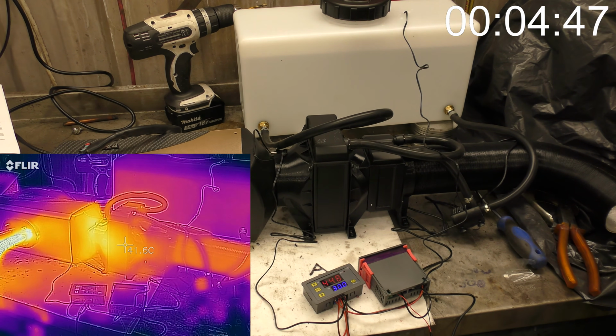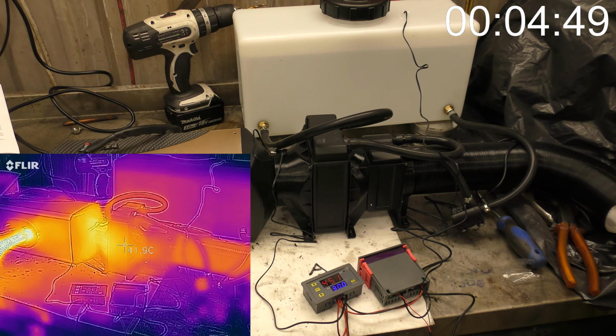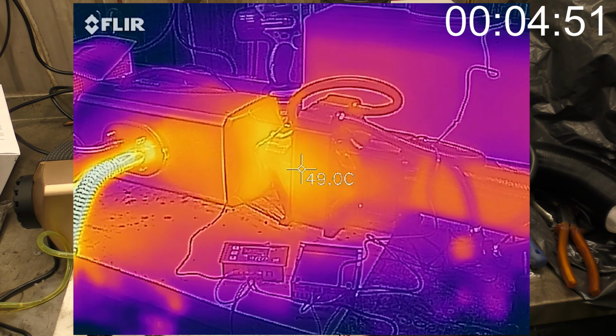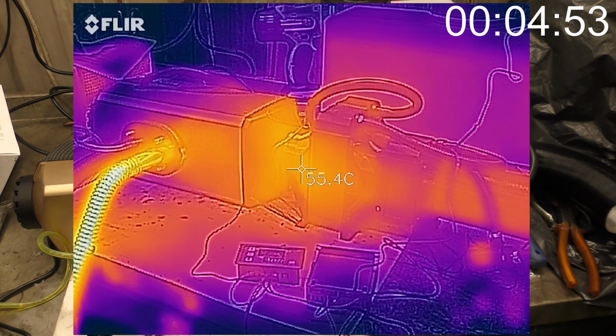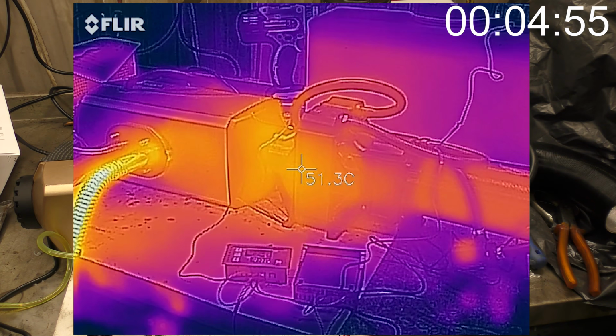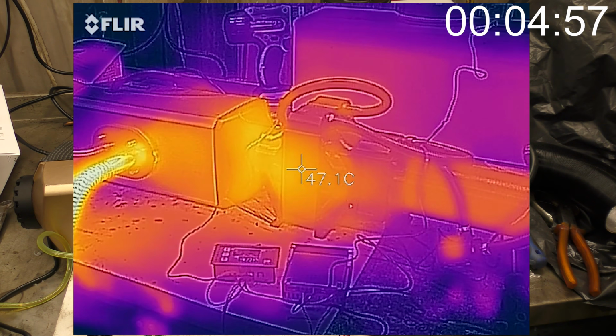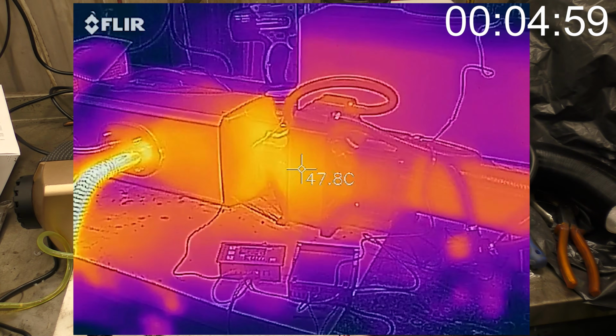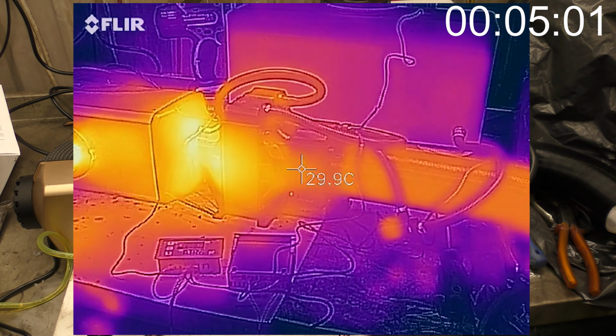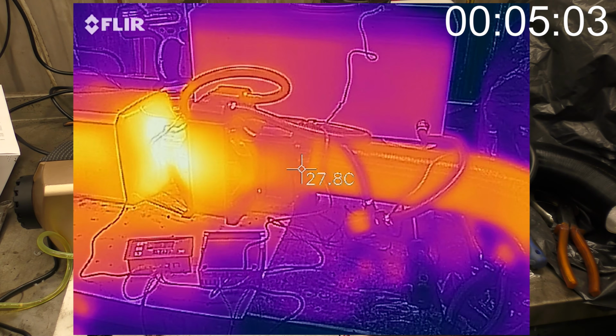Because you can see it's still in the thermal imaging, I'm going to do a sweep left to right here. The inlet temperature coming straight out of the machine is a good 55. If we come over here just a little bit, let me slacken that. So you swing around, see that? That's 27 degrees.